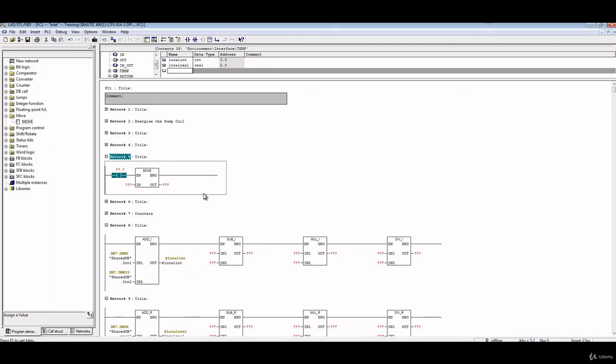So the operator on the HMI can press a button. That button will be that logic, that bit value. Once he presses the button, this logic will be true, so we load the value which is in the input to the output, just in a pulse. This will be a pulse, from 0 to 1 and from 1 to 0 again in 1 second. Then it will load the value here to the output. In that case, the set point is loaded only once, and then the operator can change the set point to whatever he needs. But it serves as a safe operating point.